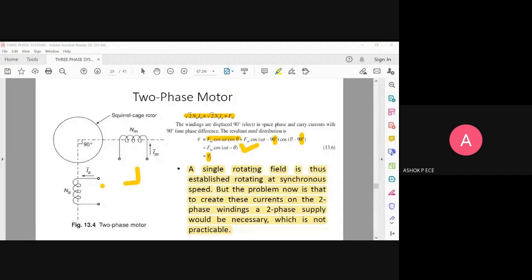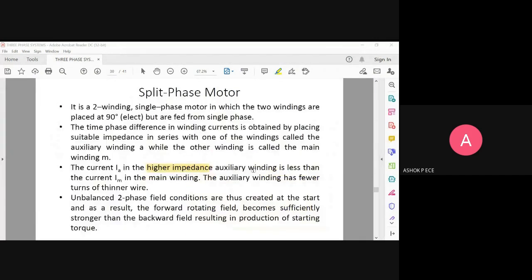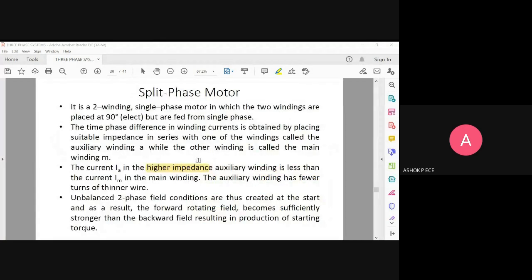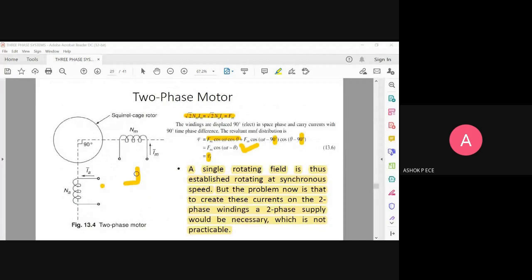In the previous case — two-phase and split-phase — it is the same motor. But in the two-phase motor, the main and auxiliary windings are identical; the parameters are exactly the same. In the split-phase motor, the main winding has less impedance and the auxiliary winding has more impedance.